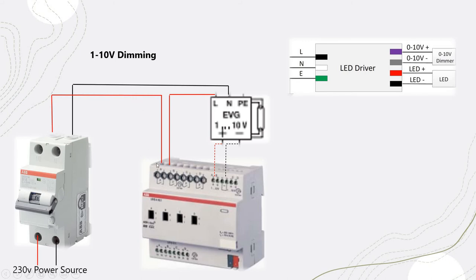For the 1-to-10V dimming wiring, you take the live cable from the electrical DB to the input of the channel. The live from that channel goes to the driver — the 0-10V light requires a driver. The neutral goes directly to the electrical DB. You then pull a communication control cable — the same 1mm two-core or 1.5mm two-core cable used in BMS — from the 0-to-10V control signals to the light driver. You can loop to the next bulb, so ten lights in one room can be looped together as one spotlight circuit. Channel B follows the same method.